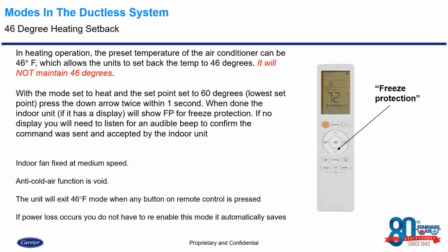Okay. So usually what I tell guys is that the setback modes on ductless really don't save you much money. And here's the reasoning behind it. With these systems, because they are inverter based, they are only drawing the amount of power necessary to be able to heat or cool that space. So if it's wintertime and we're allowing a space to go down to, let's just say 48 degrees, and the system never kicks on, and then you come back in there and you want to start doing work, whether it's a garage or just an area that really doesn't have to be maintained or that is temperature critical. If we have 48 degree space temperature and you want to bring it up to 65 degrees, you've got a heck of a threshold that you've got to catch up on. So that system's going to be doing a lot of work. It's going to be pulling a lot of power, depending on how much we ramp up that compressor. Versus if we set it back a couple degrees and let that inverter do what it does best and maintain. It's a lot cheaper to maintain temperature than it is to try to run a machine at full frequency to catch up from a 48 degree room temperature to a 65 degree room temperature.